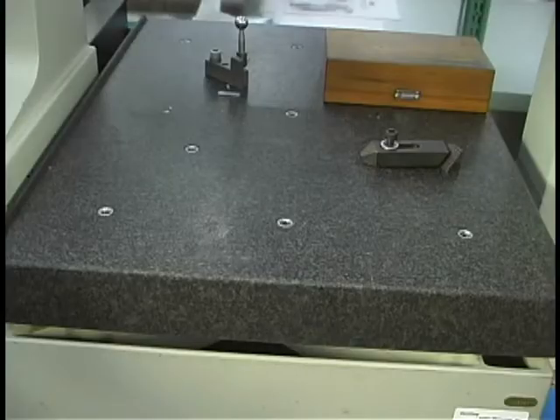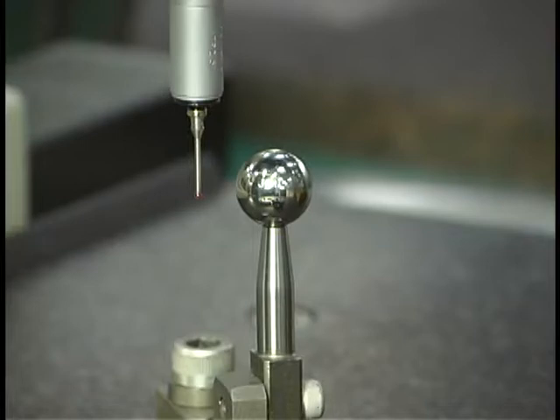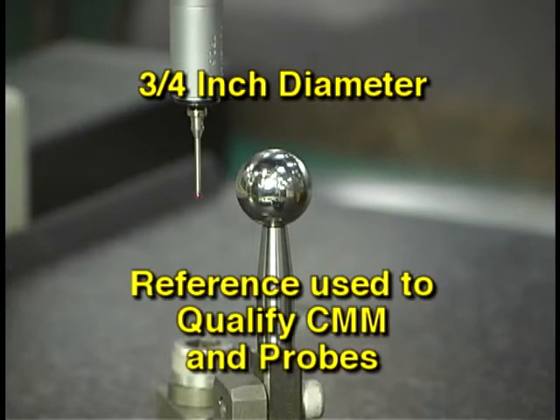The surface plate has holes with threaded inserts for placing mounting clamping devices. This is the qualification sphere. It is 3 quarters of an inch in diameter, precisely manufactured sphere. It is secured to the surface plate and used as a reference device to qualify the CMM and the probe being used before measurements begin.